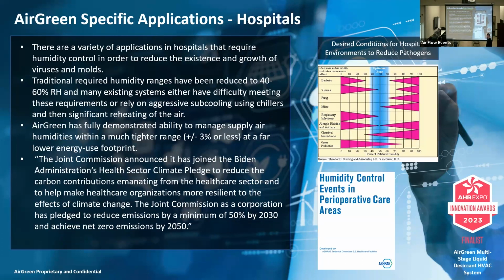Are you guys working on tools where, if I plug in my reactivation temperature and my air conditioning fluid temperature and my airflow, it tells me this is the kind of dehumidification I should be able to get, or do you have to do all the designs? No sales tools yet, it sounds like. Okay, so right now we've integrated Delta controls into our system. We like them because they're non-proprietary and anybody can use them. We are building an algorithm now where you can put it into energy savings mode and sort of start trimming some things. But early on, everything was, if you need to run, cycle between units as necessary and turn down a little bit.